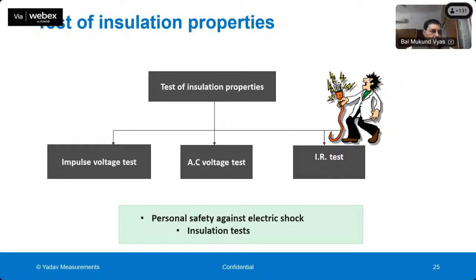Right. Another series of tests which the meter has to pass through is the test of insulation properties, which is basically for the safety of the users of the electricity meter. It should not happen that, with a smart meter or a normal meter, when you try to read the meter or see the display, you get a shock. Similarly, if a meter reader or somebody is coming to inspect the meter or test its accuracy, because accuracy can be tested at site also, they should not get shocked when they touch the meter for a push button or connecting the supply and so on. So the insulation of the meter has to be properly tested.